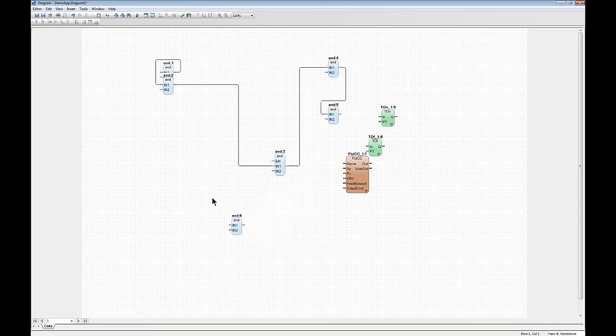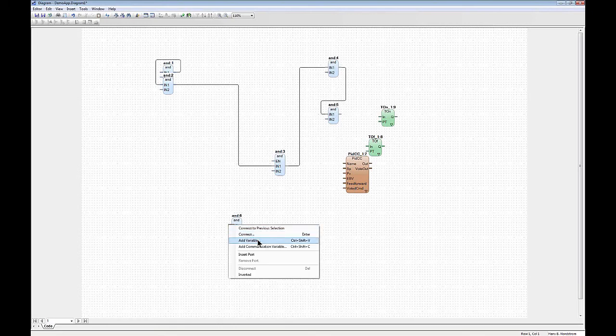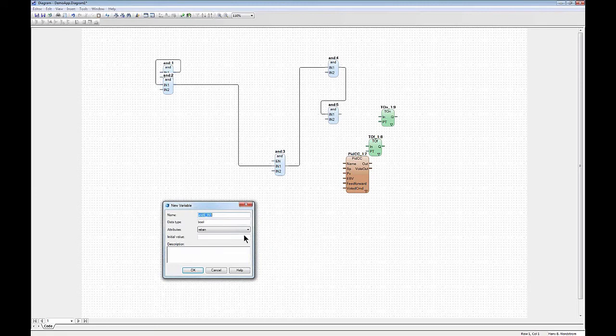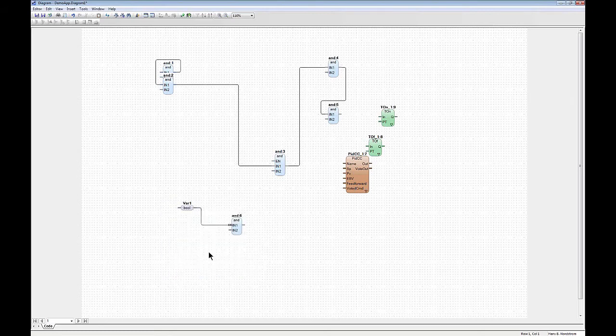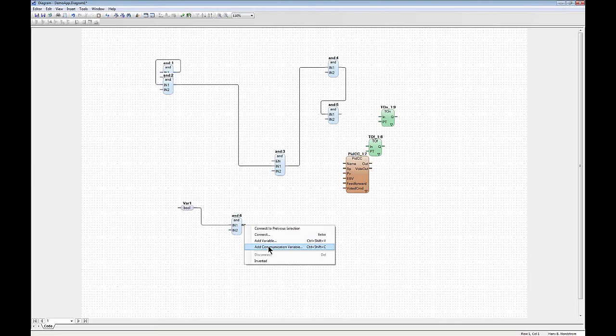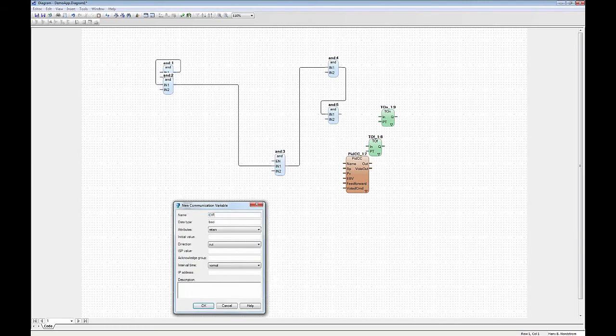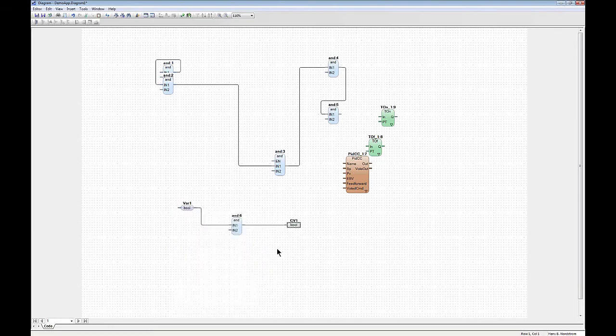When you want to connect to a variable, simply click on the port. The editor will suggest a name based on the block name and port name, but let's call it 'variable one'. You've now created and connected a variable in one stroke. Similarly, if you want a communication variable, click a port and select 'add communication variable' — call it 'CV one'. This produces data that can be used anywhere in this diagram, this application, or anywhere else on the whole network.